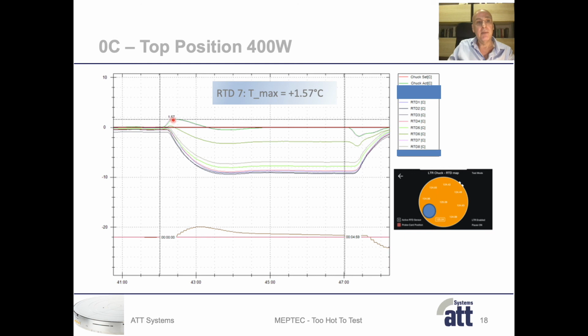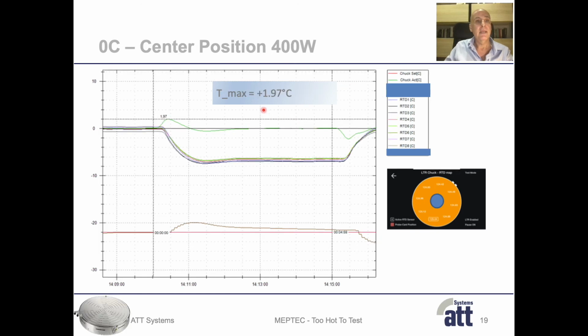And then the system is able to fully dissipate the energy and to stabilize the temperature very close around the set value of 0 degrees C. The other temperature sensors can be ignored because they have no impact on the contact area. This graph shows the results at the center position. So after applying the power, the temperature increased to around 2 degrees C, and then the system fully dissipates the energy and can control the temperature very stable around the set value.